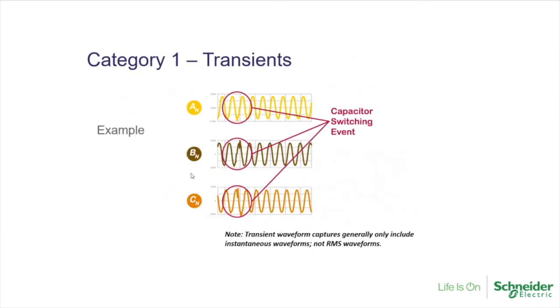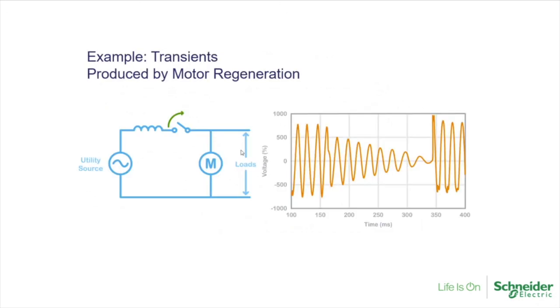Another category is transients. Hopefully you can see these pretty well. The one in the middle is probably the easiest. You can see that it peaked up at the top. A transient is very short term. They can have really high magnitudes, especially lightning strikes. And the thing you're more or less concerned with here is, you haven't heard of a lot of customers losing power when transients hit, but it is putting a significant amount of voltage on your system, even if it's only instantaneous. And essentially, anything struck by lightning too many times isn't going to fare well too long after.